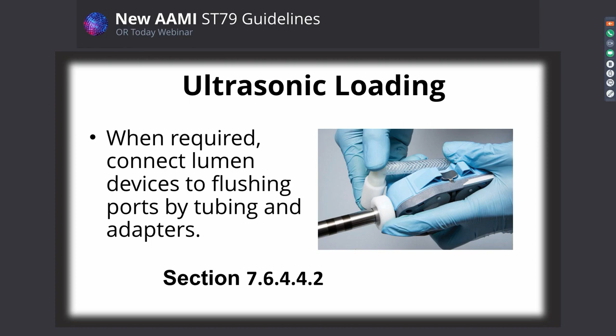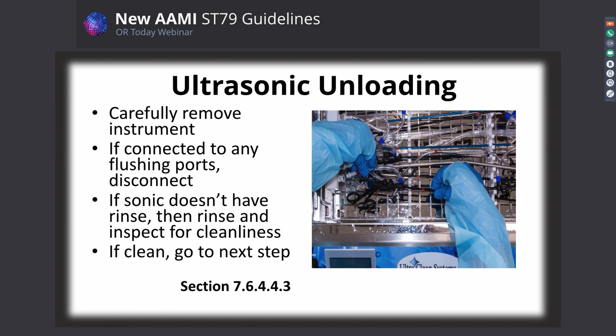When you're unloading your system, carefully remove instruments. I think that doesn't necessarily need to be stated, but again, it's in the document for you. If connected to any flushing ports, of course, disconnect those. Do so carefully. And if the sonic doesn't have a rinse, then rinse and inspect for cleanliness. And if it's clean, go to the next step. Verification of the cleaning process. This is also a little bit more thoroughly stipulated in ST79.